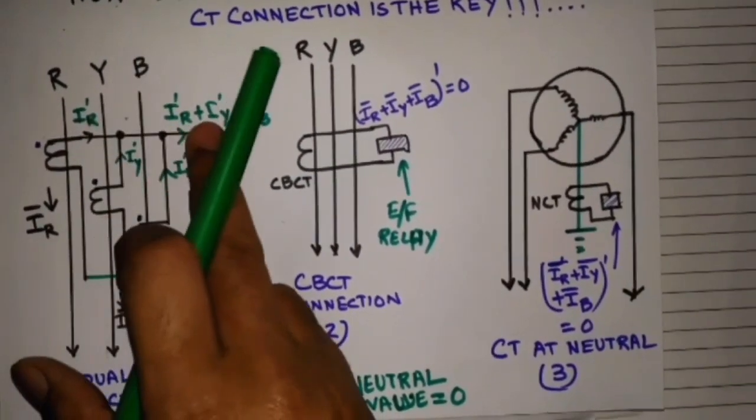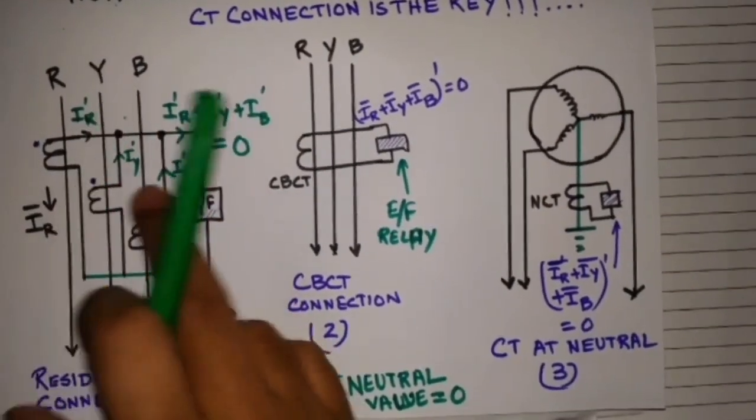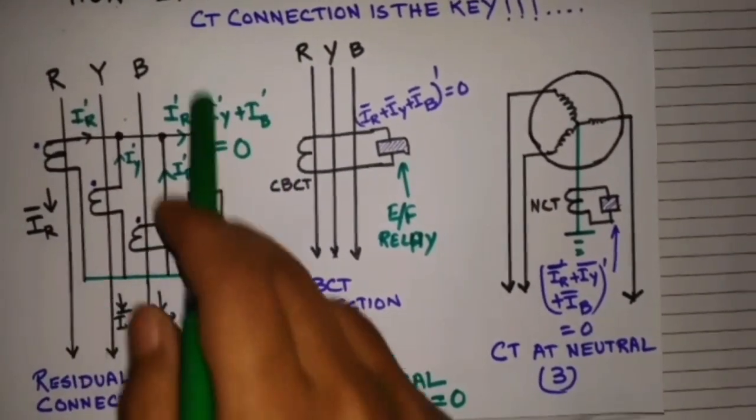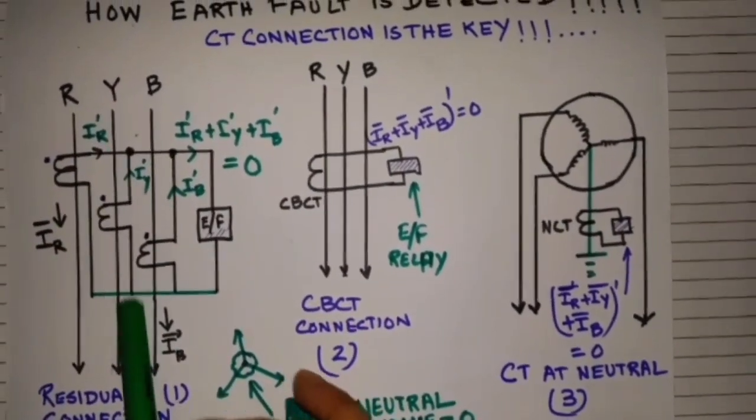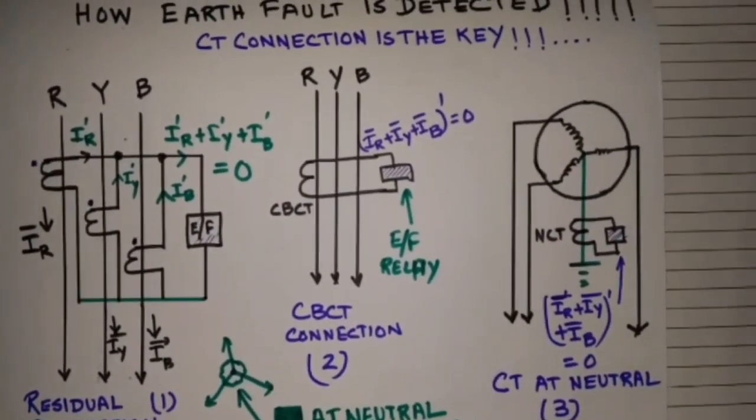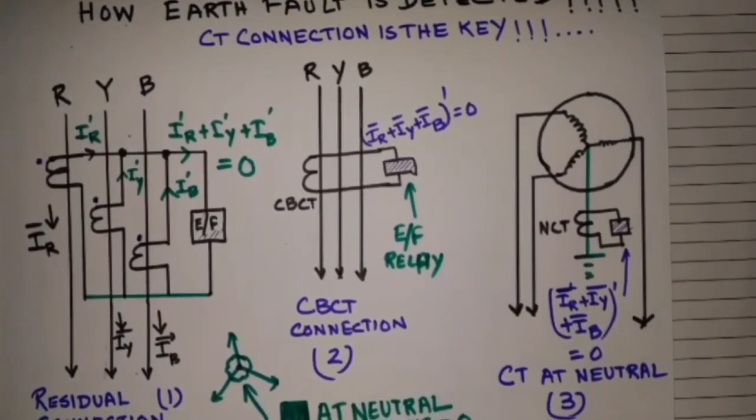So these two will oppose each other in their summation. So for that case, the relay will not pick up. For this type of connection, only if there is an earth fault, then only the relay will pick up. For any other fault, the relay will not pick up.